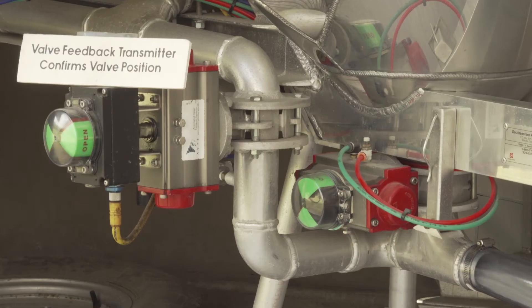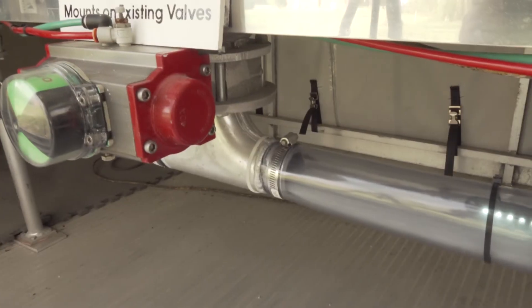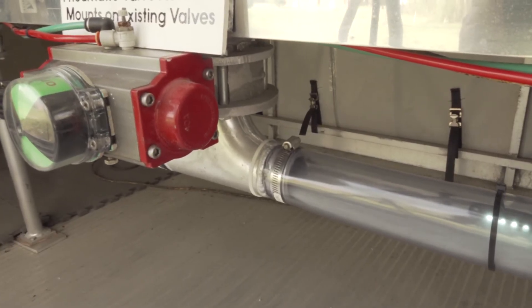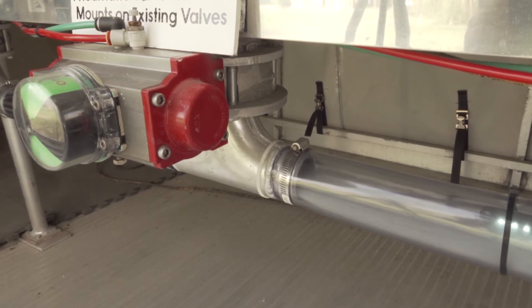When the tank pressure drops to 7 psi, it will automatically close the first hopper and open the next hopper. While unloading, if the line pressure starts to climb, the computer will prevent plugs from happening by opening the line valve 100% and closing the hopper valve.